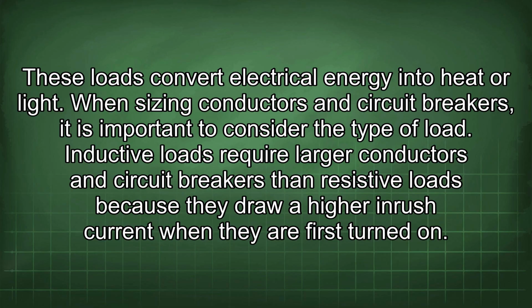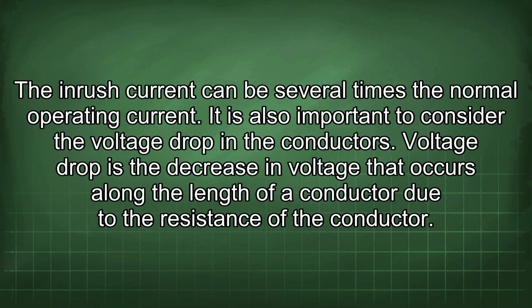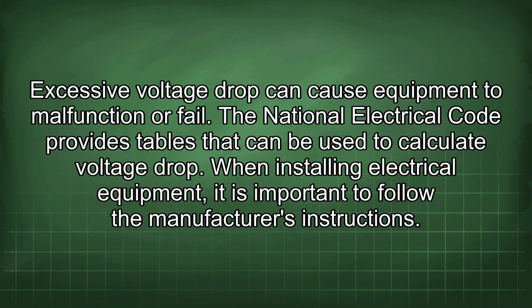When sizing conductors and circuit breakers, it is important to consider the type of load. Inductive loads require larger conductors and circuit breakers than resistive loads because they draw a higher inrush current when they are first turned on. The inrush current can be several times the normal operating current. It is also important to consider the voltage drop in the conductors. Voltage drop is the decrease in voltage that occurs along the length of a conductor due to the resistance of the conductor. Excessive voltage drop can cause equipment to malfunction or fail. The National Electrical Code provides tables that can be used to calculate voltage drop.